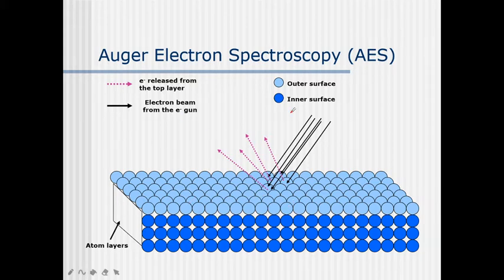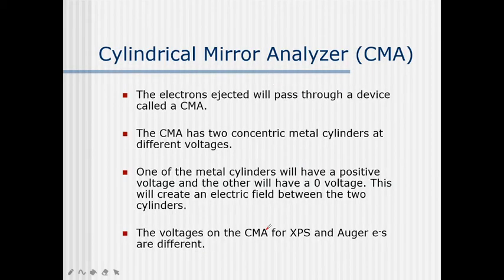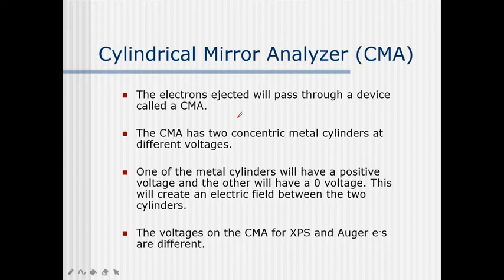An electron beam from an electron gun falls on both the outer level and the inner surface. Electrons are released from both the inner and outer layers of the atom. These released electrons can be analyzed by cylindrical mirror analyzers (CMA). The ejected electrons pass through an analyzer device. The CMA has two concentric metal cylinders at different voltages.